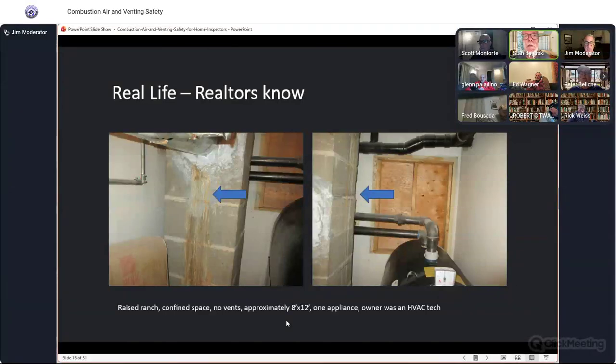So I told the realtor and the buyer, look, you could take combustion air out of this room if it met the proper requirements. So you may want to tread softly when you question this guy about it. It doesn't hurt to put louvers in to make sure you got enough air coming in here. And I know why he didn't want them, because he had a beautiful downstairs room where he probably entertained, and he didn't want to hear the boiler running.